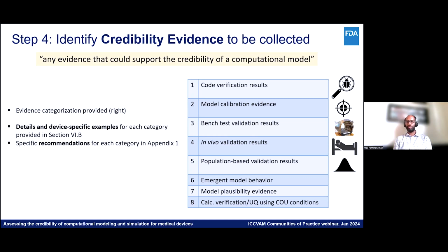Now, typically this is done as part of a model development process, but a good fit to the calibration data could be generally supplementary evidence in support of the credibility of a computational model, especially when it's a relatively simple mechanistic model that well matches kind of complex behavior. But we emphasize that calibration is not validation.